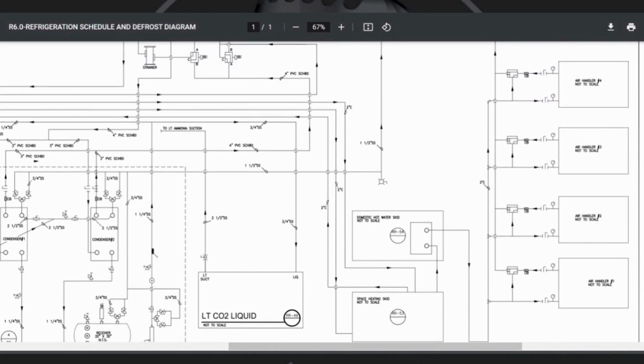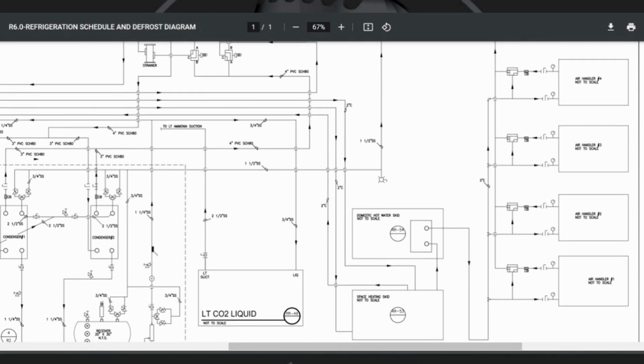there isn't a central glycol pump like is shown here. At each air handler there is a little board about maybe 2 foot by 3 foot, and on it is mounted a little tiny plate heat exchanger, a circulator, and a liquid solenoid for the CO2 side. And you have a CO2 connection, and right at the air handler, when you want cooling, you turn the pump on, the fan runs all the time, and then you open the liquid solenoid and you achieve your cooling.